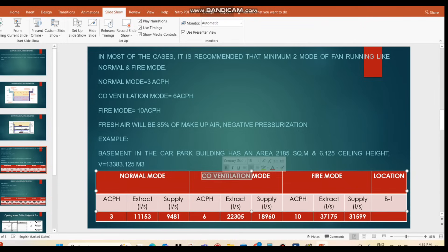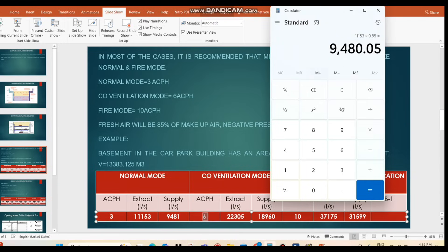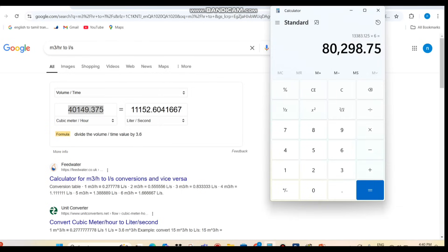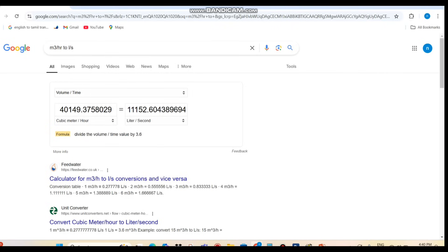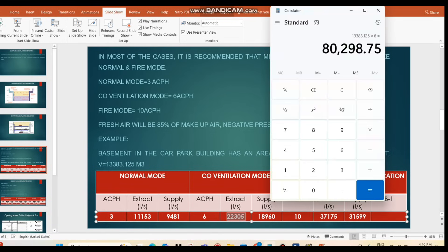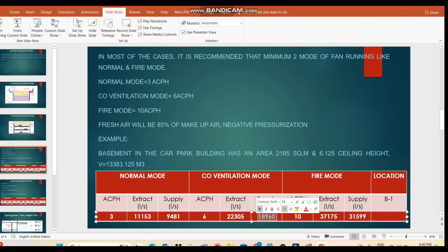For CO ventilation mode at 6 ACH: 13,383.125 × 6 gives the result in cubic meters per hour, which converts to approximately 22,305 L/s exhaust, with supply air at 85% giving approximately 18,959 L/s. Similarly, for fire mode at 10 ACH you can calculate the same way. This covers the simple calculation; now we will discuss the practical issues.